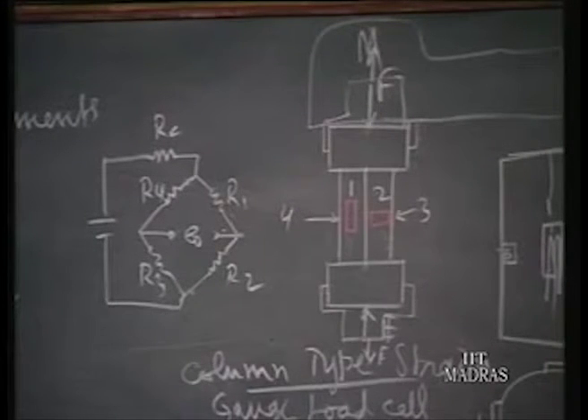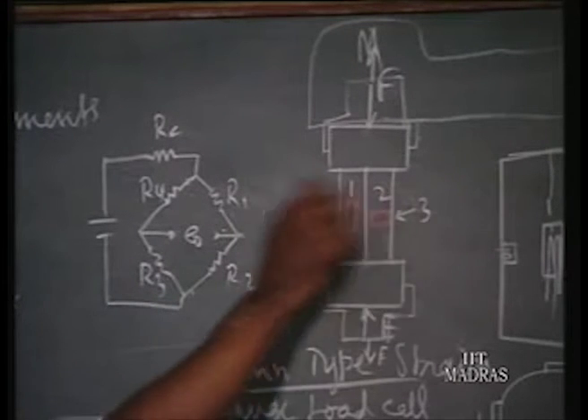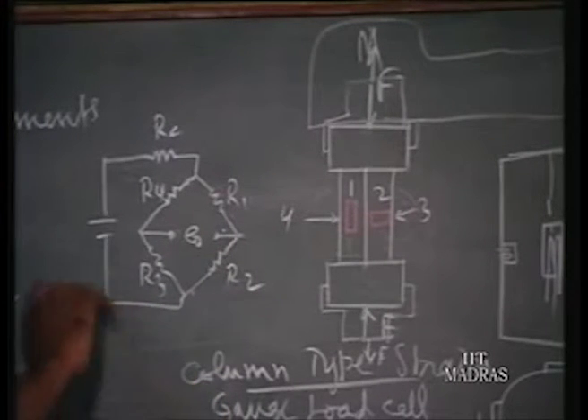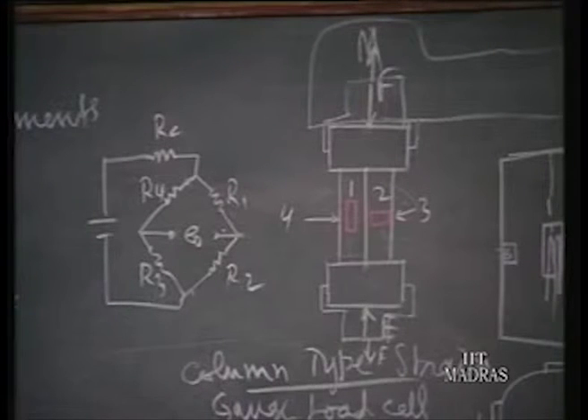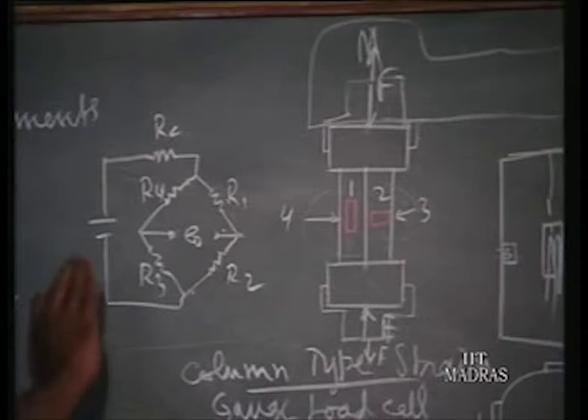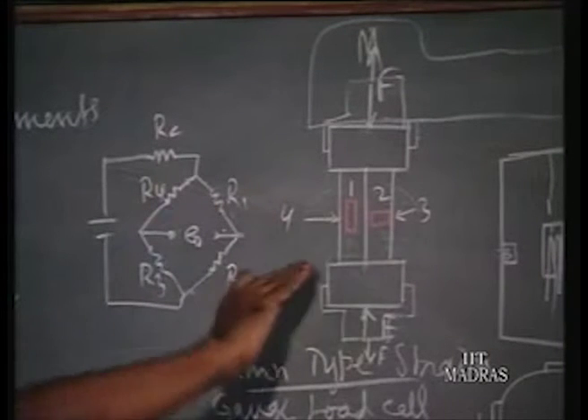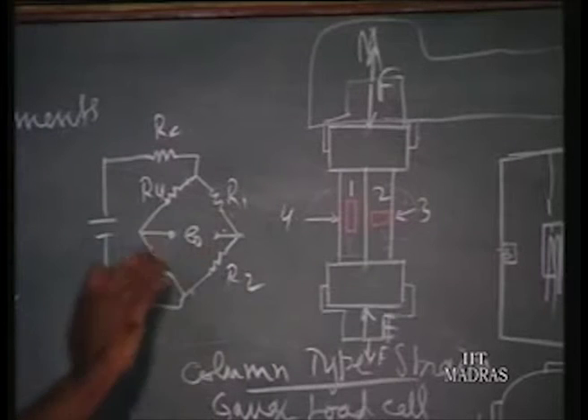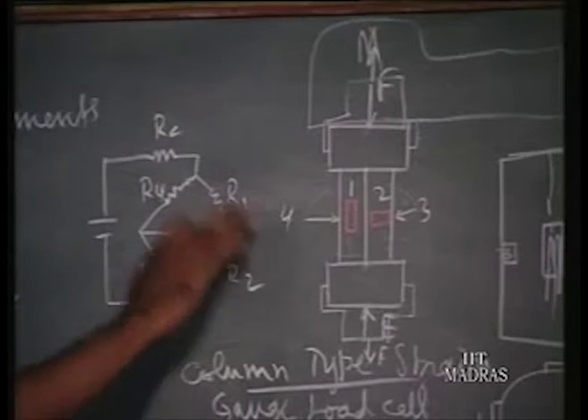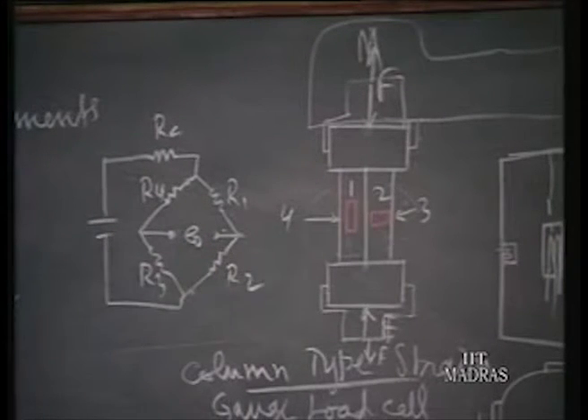Now this instrumentation we find is insensitive to temperature variations, because it's a full bridge. All the 4 strain gauges are under the same temperature conditions. So you find temperature compensation is already there. There is no need for any dummy gauge, because temperature brings the same effect in all the strain gauges. Any same effect on all the strain gauges will give rise to 0 output, we know already. So temperature is taken care of.